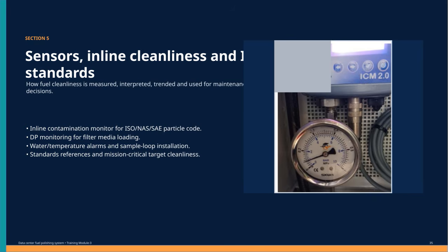We'll cover inline contamination monitors that track particle levels according to ISO, NAS, and SAE codes, ensuring we meet strict cleanliness requirements. We'll also discuss differential pressure monitoring, which helps us understand filter media loading and when filters need attention. Additionally, water and temperature alarms, as well as sample loop installations, play a crucial role in detecting contaminants early. Throughout this section, we'll reference important standards and highlight mission-critical cleanliness targets that keep your data center fuel system running smoothly and reliably.